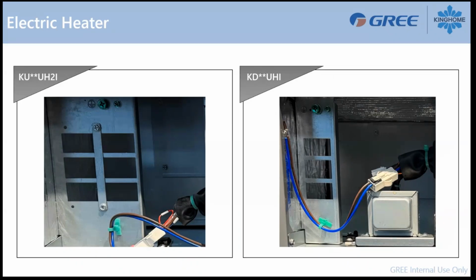On some duct heater installations, when it's time to install the breaker, you will have this metal hanger for the breaker. We have a split here with two screws. If you're using 10 kilowatt or less, there is only one breaker that comes with it. So you have to keep this black metal sheet, so metal bracket, in place. Install your breaker. But if you have 15 kilowatt and more, so 15 and 20 kilowatt, you will have two breakers side by side. So you need to remove this metal strip here to make sure your breakers will be touching each other, so they will be side by side.